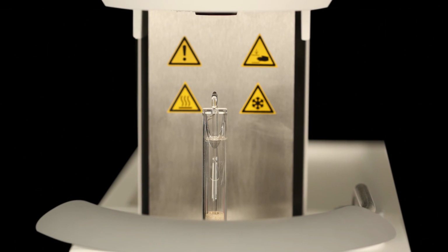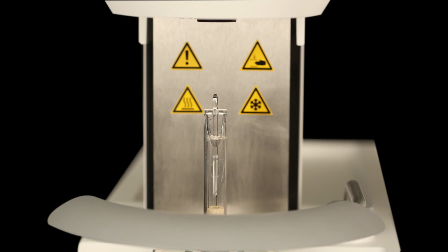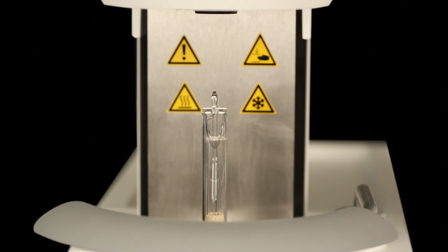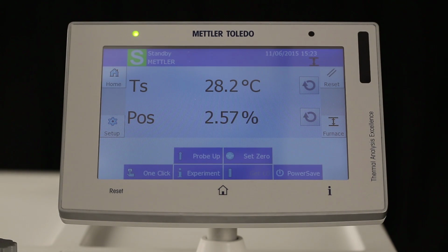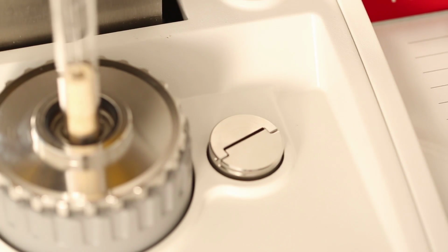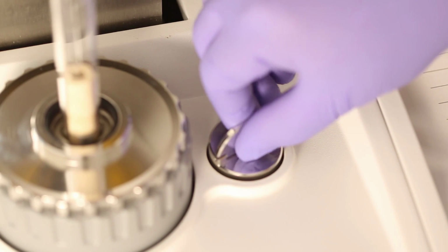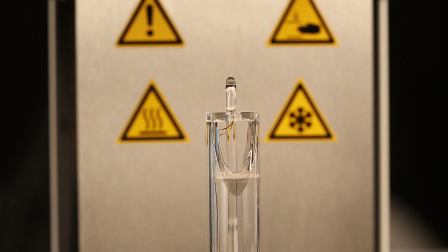For the force adjustment, the measuring cell must be thermostated with the circulator for at least 2 hours before performing force adjustment to ensure that the parts of the force generator and linear motor are at the right temperature. During force adjustment, the protective cover over the calibration weight must always be removed. The probe must be completely free to move during adjustment.